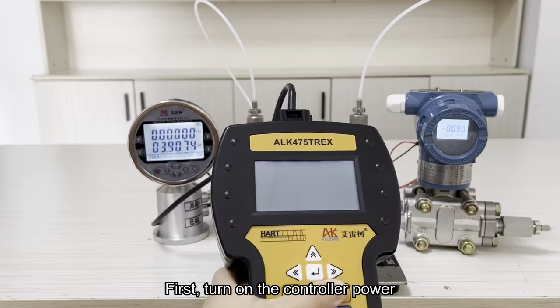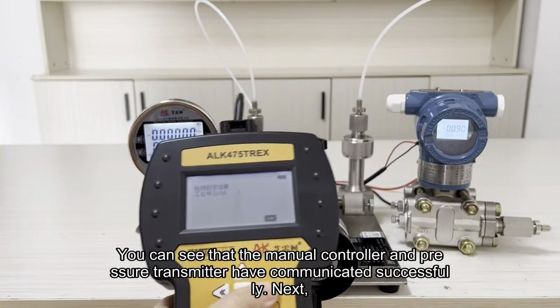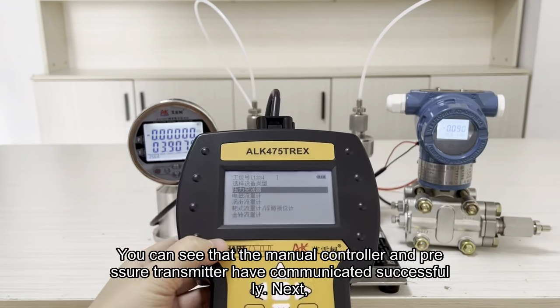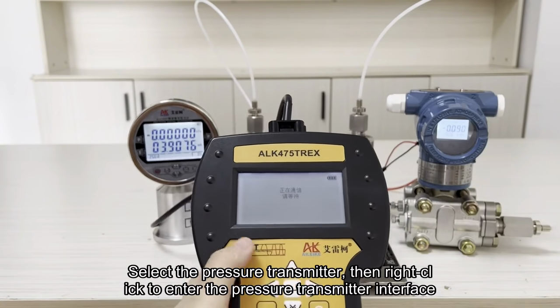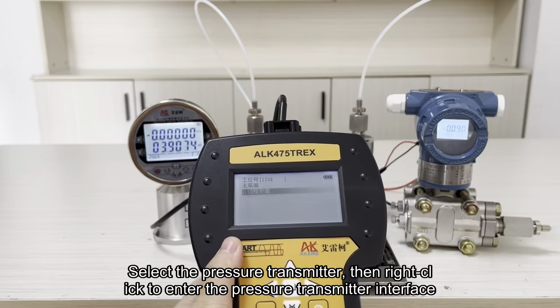First, turn on the controller power. You can see that the handheld controller and pressure transmitter have communicated successfully. Next, select the pressure transmitter, then right-click to enter the pressure transmitter interface.